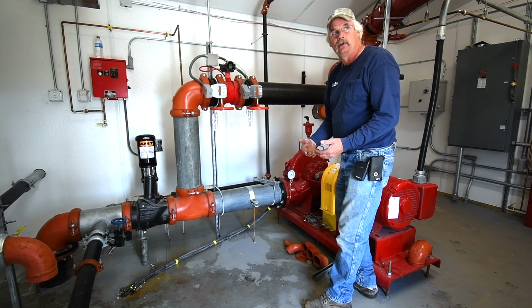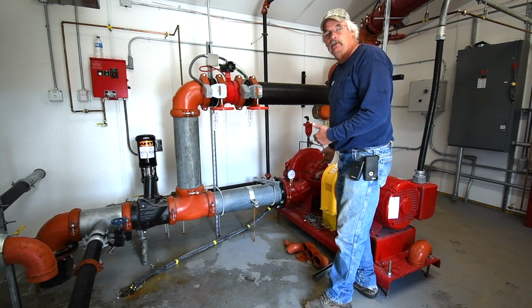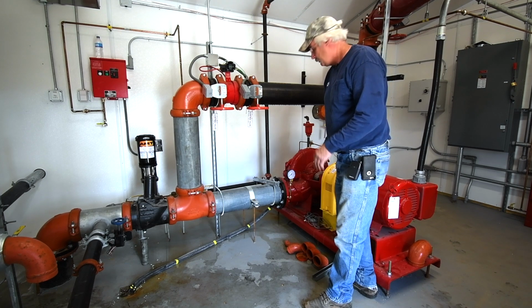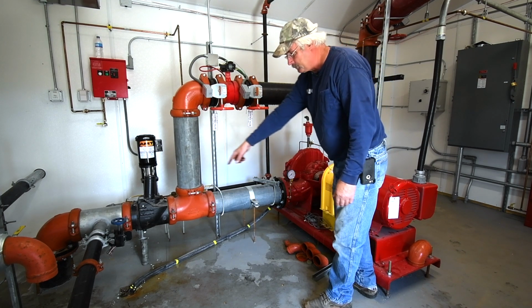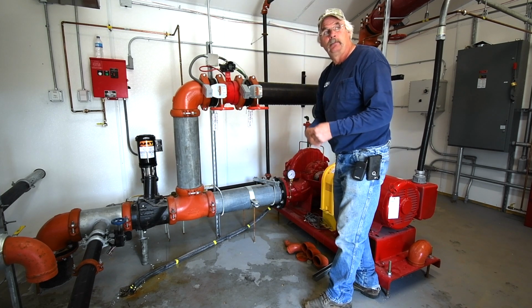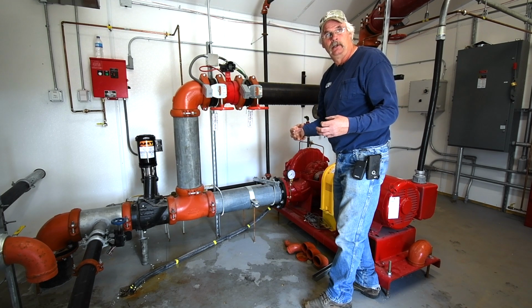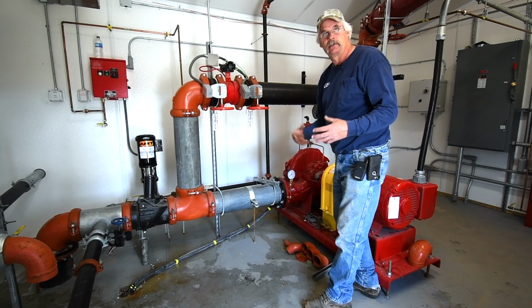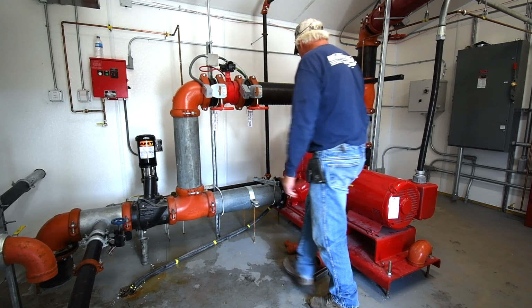So when the fire pump's running, it uses its own water to keep the shaft cool. The other thing, it has a relief line that's piped to the floor drain. So when the fire pump is running, it dumps pressure off into there so it doesn't heat up the casing of the fire pump here.